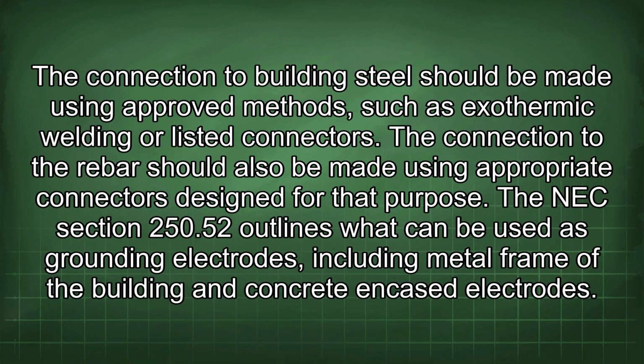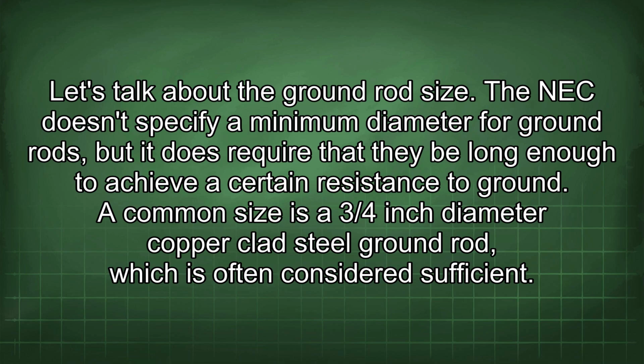The connection to building steel should be made using approved methods such as exothermic welding or listed connectors. The connection to the rebar should also be made using appropriate connectors designed for that purpose. The NEC section 250.52 outlines what can be used as grounding electrodes, including the metal frame of the building and concrete-encased electrodes. Let's talk about the ground rod size. The NEC doesn't specify a minimum diameter for ground rods, but it does require that they be long enough to achieve a certain resistance to ground. A common size is a 3/4 inch diameter copper-clad steel ground rod, which is often considered sufficient.